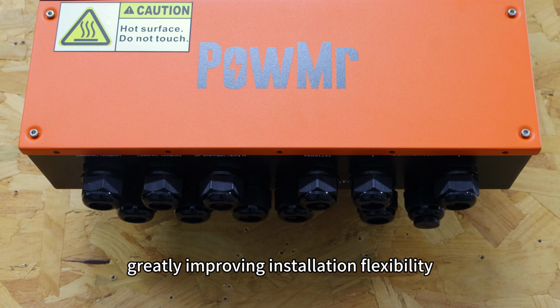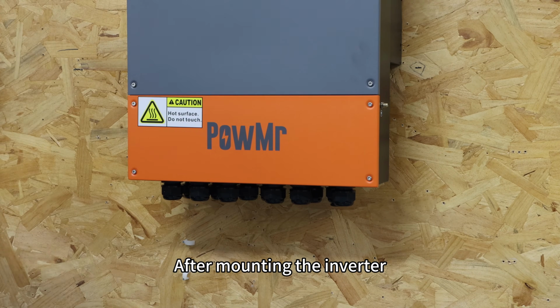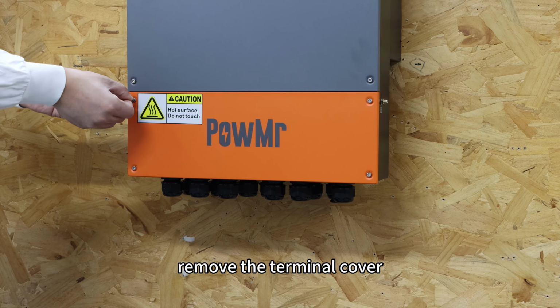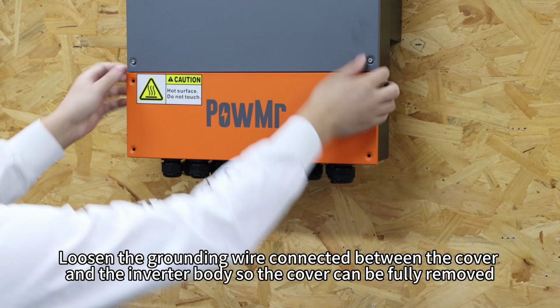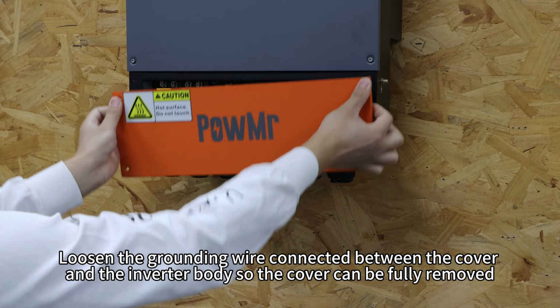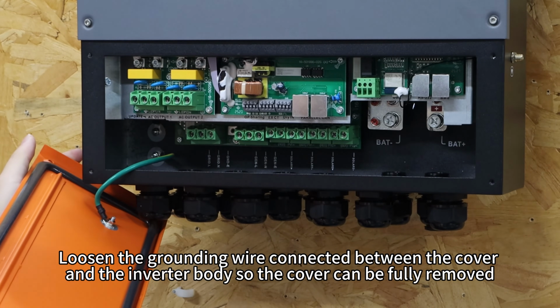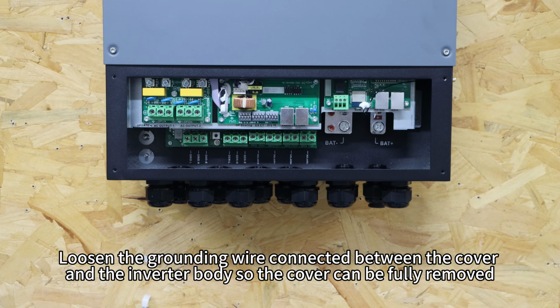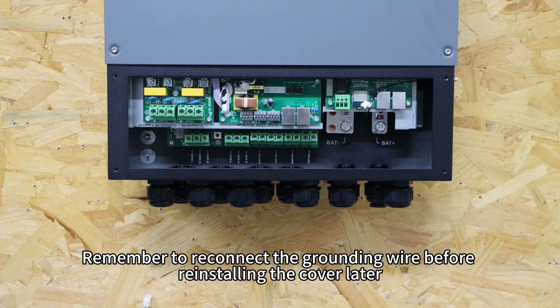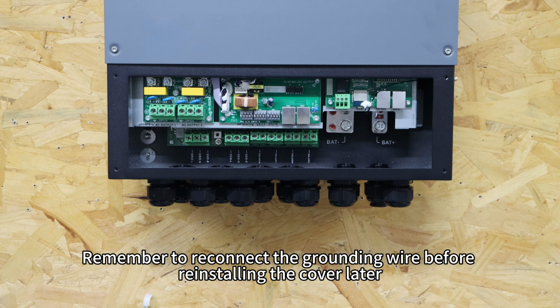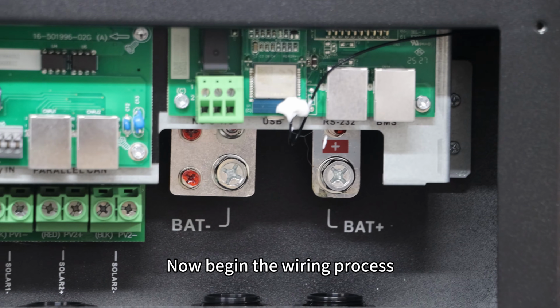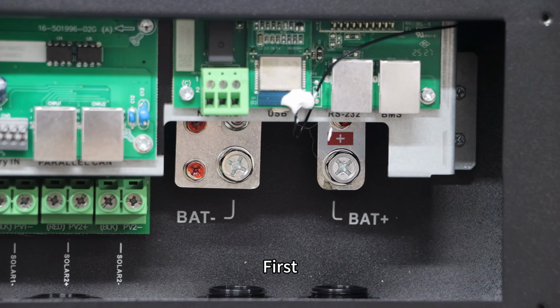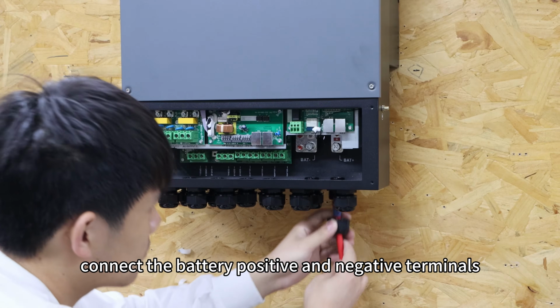greatly improving installation flexibility. After mounting the inverter, remove the terminal cover, loosen the grounding wire connected between the cover and the inverter body so the cover can be fully removed. Remember to reconnect the grounding wire before reinstalling the cover later. Now begin the wiring process. First, connect the battery positive and negative terminals.